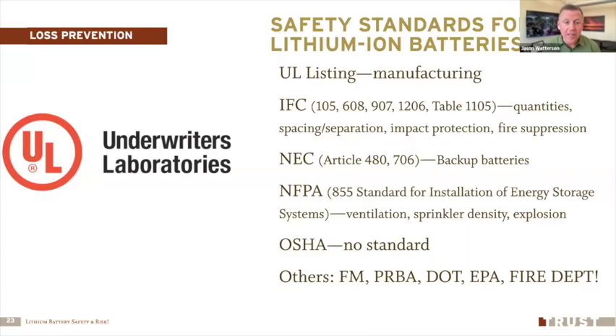National Electric Code talks about backup batteries. We had a situation here at the Trust recently where we had a UPS system fail, not in the battery. It was another part of that system that failed electronically, and it got hot enough, in our server room, to trigger our waterless system.